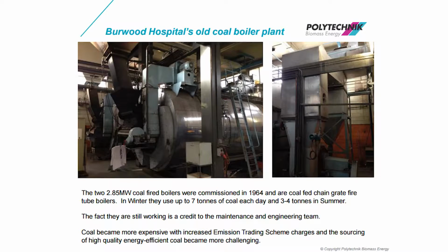So these are the existing coal-fired boilers. They're actually still there. They were installed in 1964. So the load on site changed considerably between winter and summer. So obviously the heating load was much higher in the winter. Coal was becoming more expensive, and the decision was made to look at alternatives.